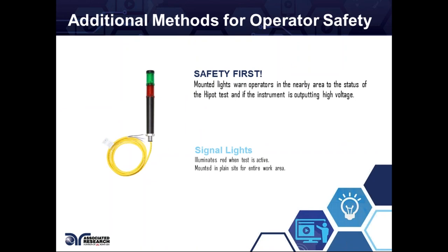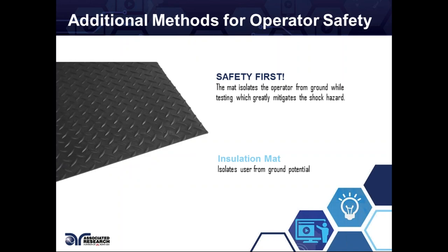The tower light is more for people who aren't using the Hipot tester but are in the area — it lets them know it's either safe to walk or not, and whether a test has passed or failed. It illuminates red when a test is active or has failed, and green when a pass signal is received from the signal output. The insulation mat isolates the operator from ground while testing, which greatly mitigates the shock hazard.